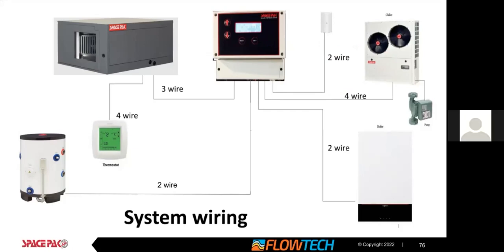Additionally, the SpacePak can manage outdoor air temperature and manage a buffer tank seasonally. So we're setting up buffer tank management. For the summertime, if the temperature is above 70 degrees, and this is all configurable, it can manage that buffer tank for chilled water. And in the wintertime, when the temperature is below 60 or below 50 or below whatever you set, it can manage that buffer tank for heating. And then it creates a dead band in the middle for efficiency. So it's managing a buffer tank seasonally. It's taking calls from the field.